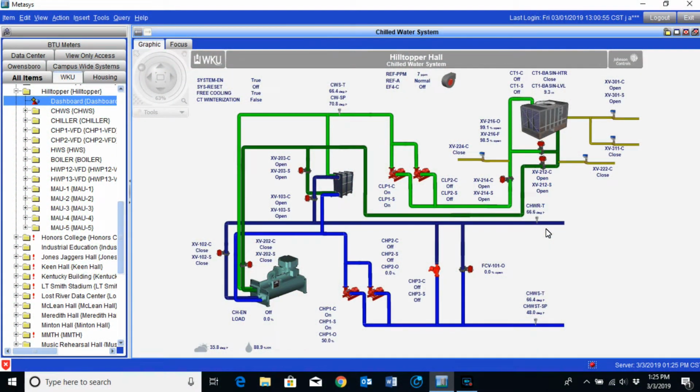In this video, I wanted to take a few minutes to talk to you all about the fundamentals of how a plate frame system works in a chilled water system. If you have a building where there are interior units that need to be supplied with chilled water that do not have access to outdoor air, a plate frame system is a very useful system to provide that water for those units, especially during the colder periods of the year.